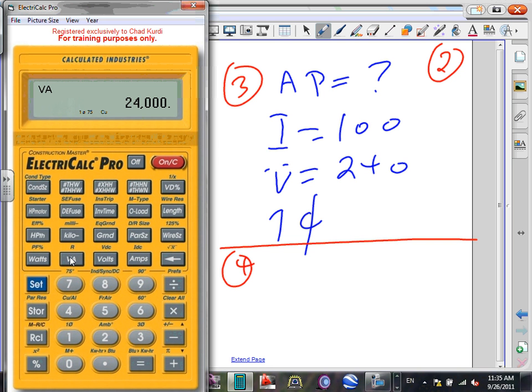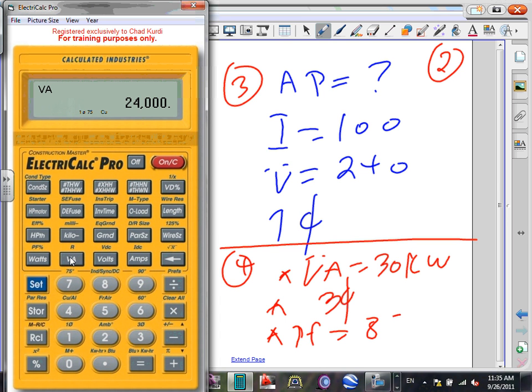Question number 4: what size transformer is required for a 30 kW 3-phase load with 85% power factor? So here's what they're asking - volt amp is given as 30... kW. This is recorded, DJ, so you can get that one too. 30 kW, phase - I have a 3-phase system, very important to know the phase. And what else do I have? 3 phase, and a power factor of 85%.